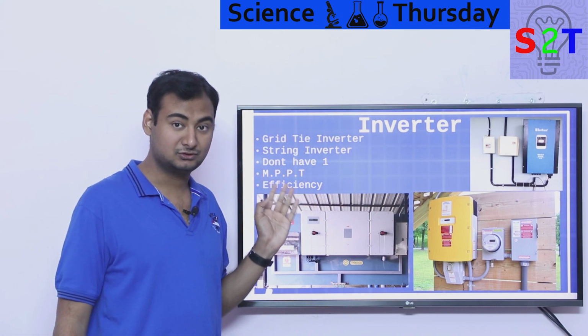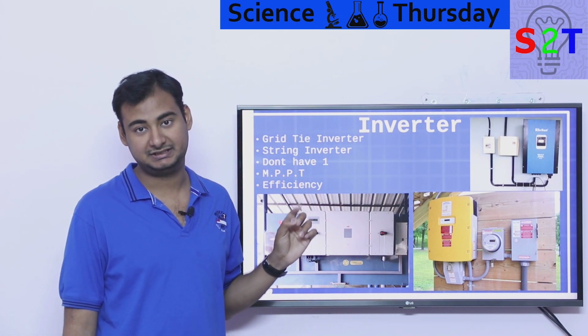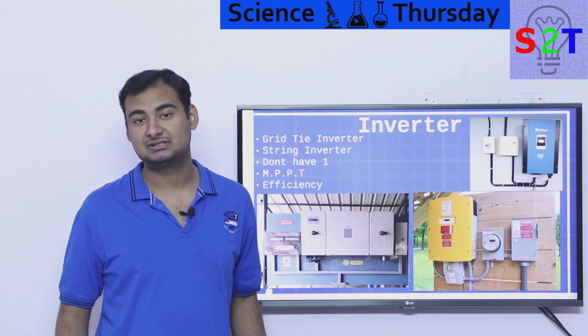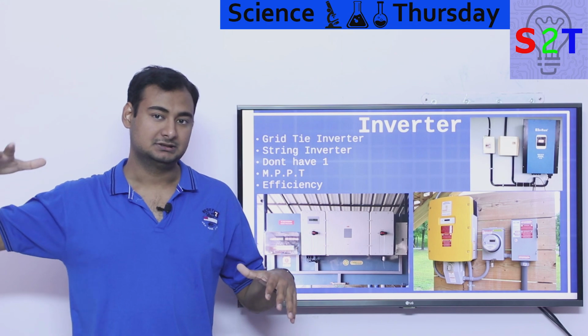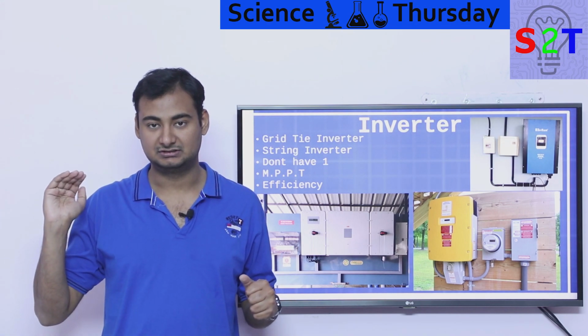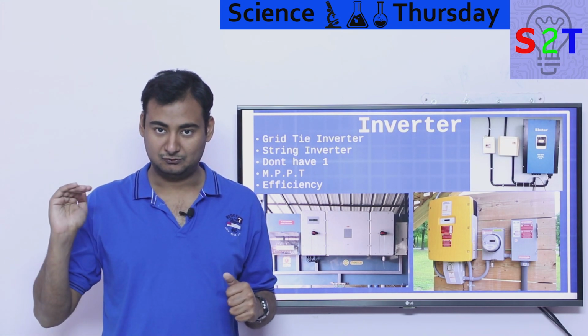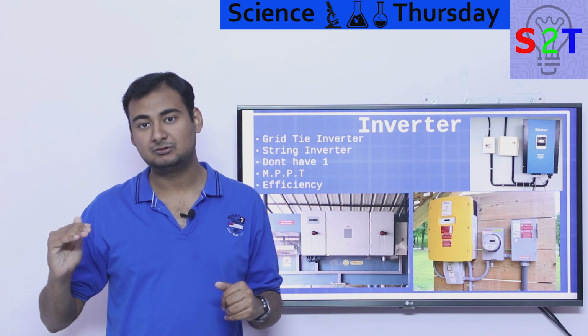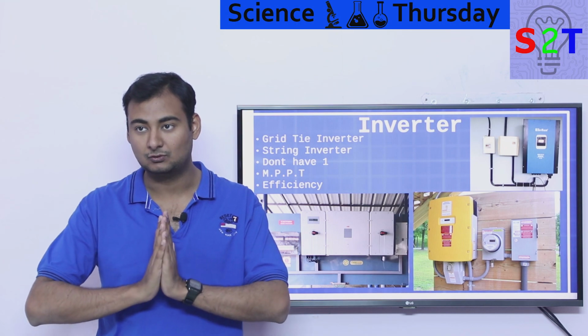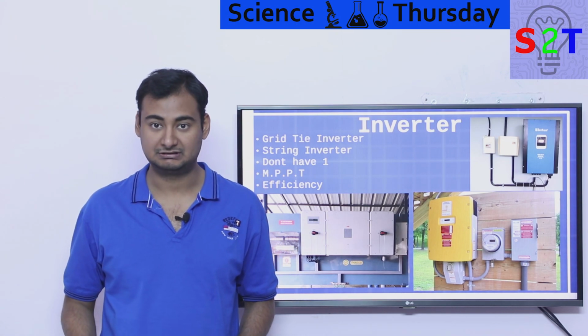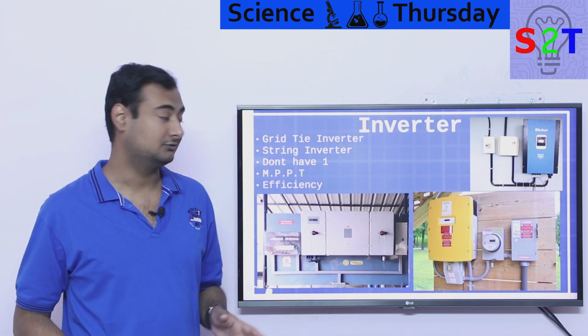Then, almost all good inverters generally have MPPT. Basically, what you have to understand is that when solar panels are shaded, let's say a cloud rolls around, the panels that are shaded reduce dramatically in their amp output, and over time even their volt output. First the amp will be compromised, then the voltage will also go down, and that could trigger a fail-safe reaction where that whole solar panel is not producing any power because it goes below the cutoff voltage.